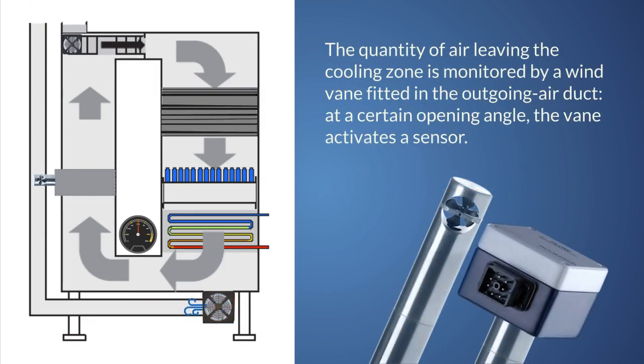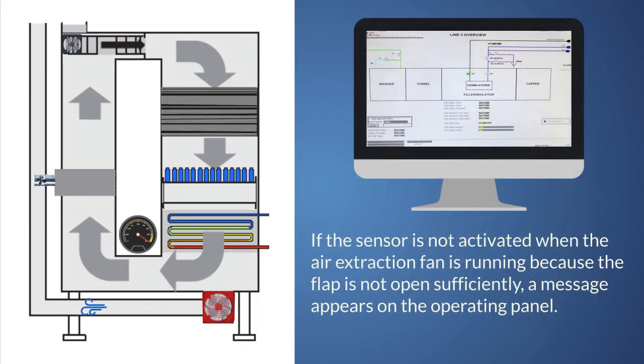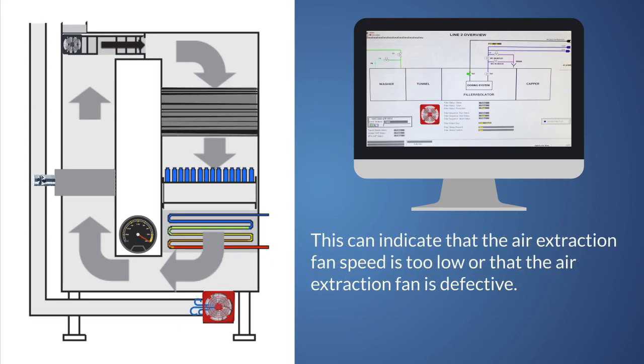The quantity of air leaving the cooling zone is monitored by a wind vane fitted in the outgoing air duct. At a certain opening angle, the vane activates a sensor. If the sensor is not activated when the air extraction fan is running because the flap is not open sufficiently, a message appears on the operating panel. This can indicate that the air extraction fan speed is too low or that the air extraction fan is defective.